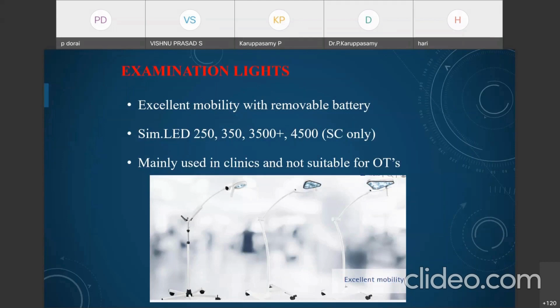Vishnu, move to the next slide. Yeah, it is an examination light. The models 250, 350, 3500, 4500 depend upon illumination. The 250 is 30,000 lux. Lux is the medical term, similar to how we use watts for home lighting. So the 250 light is 30,000 lux, 350 is 30,000 lux, 3,500 is 60,000 lux, and 4,500 is 1 lakh lux, depending on the surgery, used outside the OT.